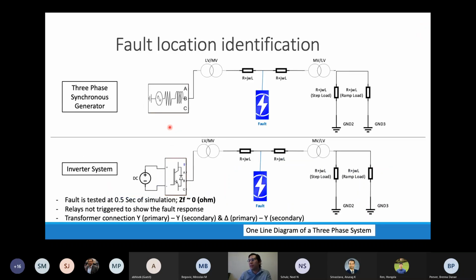So in the following figure, as before, in our study case, in our experiment, we will be testing a fault during 0.5 seconds of simulation. We are not triggering any relay because, as you can see here, they are not implemented yet. And the reason is that we want to understand the response of this generator under a faulty condition. We tested, as I mentioned, the YY and delta Y types of transformer. So here is the same grid with only the synchronous generator, and here, instead of the synchronous generator, we have the inverter installed. We are taking all the measurements at the low voltage, at the lower end of the transformer connection.